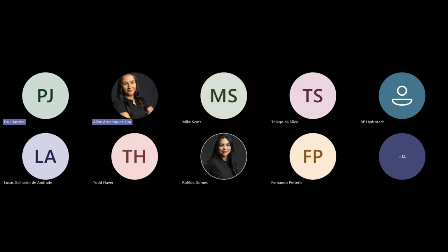Okay, thank you. Siemens. Yep. Yeah, we've worked with Siemens Energy for a long time, many years. In Germany, they buy the two different styles of our rotor ground fault system, the mid shaft system and the end of shaft system, and in both cases they use shunt measurement capability to give them average field temperature through a shunt current flow.